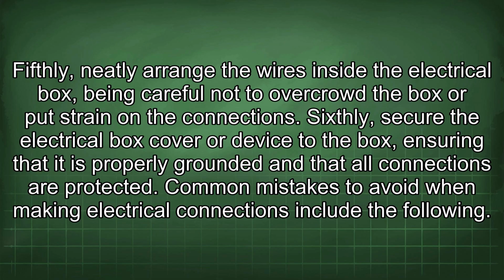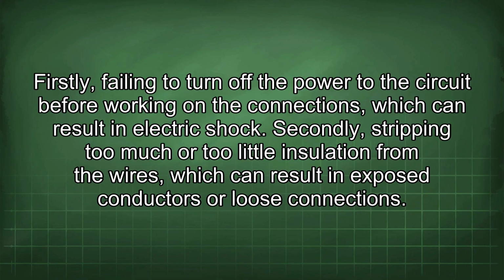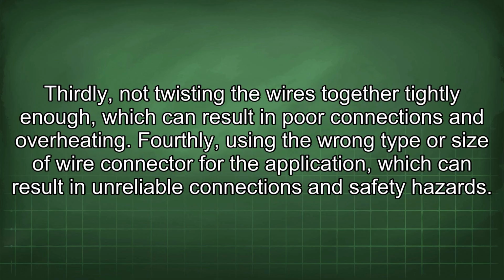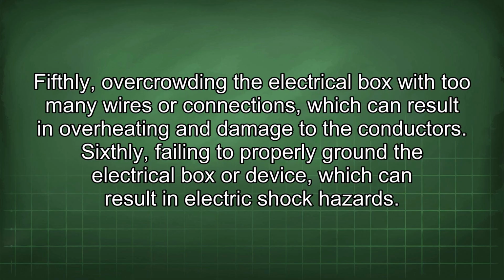Common mistakes to avoid when making electrical connections include the following. Firstly, failing to turn off the power to the circuit before working on the connections, which can result in electric shock. Secondly, stripping too much or too little insulation from the wires, which can result in exposed conductors or loose connections. Thirdly, not twisting the wires together tightly enough, which can result in poor connections and overheating. Fourthly, using the wrong type or size of wire connector for the application, which can result in unreliable connections and safety hazards. Fifthly, overcrowding the electrical box with too many wires or connections, which can result in overheating and damage to the conductors. Sixthly, failing to properly ground the electrical box or device, which can result in electric shock hazards.